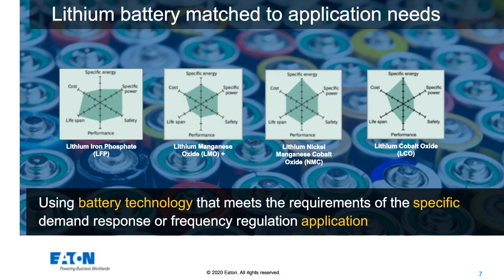That's an important reason to choose a lithium battery for a UPS, but the most common reason, besides the small size and light weight, is the high ability to charge and discharge repeatedly without wearing those batteries out. Traditional UPS batteries can provide a few hundred charge-discharge cycles and they're done, whereas lithium battery vendors tell us they can handle as many as thousands of charge-discharge cycles over a 10 to 15 year life. That capability opens the door for lithium batteries to be used in applications where the UPS is being used as an energy management device and may need to charge and discharge its batteries multiple times a day, dozens of times a week or a month.